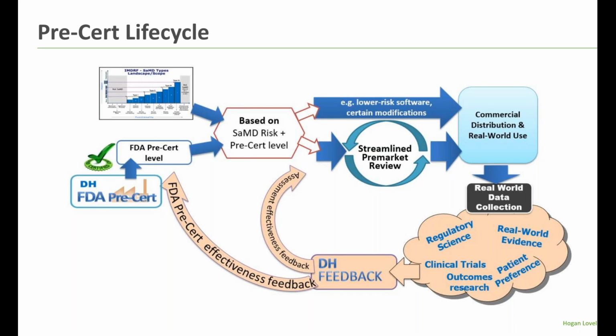So the historical view right now, without this new framework that FDA is working on, is that if you change the algorithm in a 510(k) or de novo cleared product, you have to go back again. Change the core algorithm, you have to go back for a new submission. The goal of what FDA is working on is to develop a framework so that companies wouldn't need to do that, because they would have agreed with FDA on procedures for changing it during the initial review.